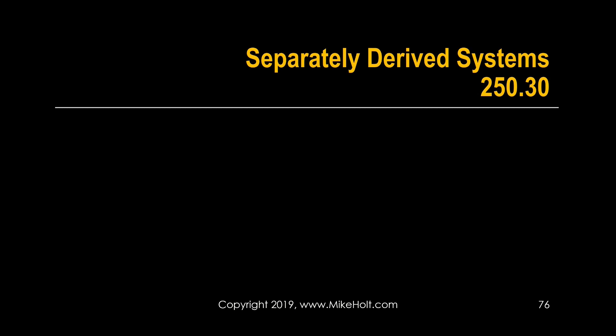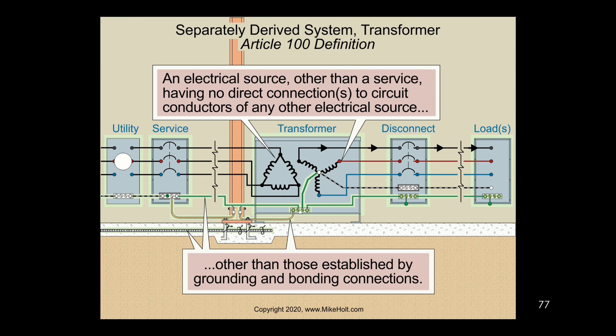Let's talk about separately derived systems, NEC 250.30. Before we get into 250.30, let's look at the definition. This is the primary winding, and there's magnetic coupling between the primary winding and the secondary winding — that's a transformer. Because there's no direct electrical connection between line one, line two, line three and the neutral directly to any of the line conductors coming in, this is called a separately derived system.